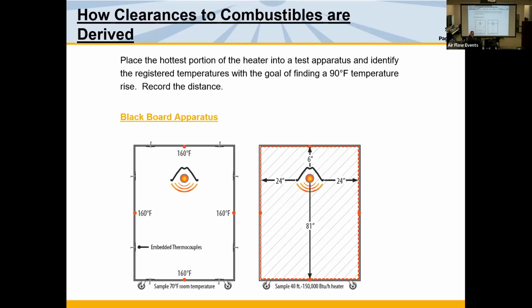Probably one of the biggest problems we have with sprinklers is on patios that are sprinklered, because the trip point on a lot of sprinkler heads starts at 160. So if you have a 60 degree night, putting a heater plus 90, you're pushing up to the limits. You can get different color sprinkler heads, and very often on the sprinkler heads for patios, I recommend the red one, which is 230 degrees. It keeps people out of trouble. Next slide.